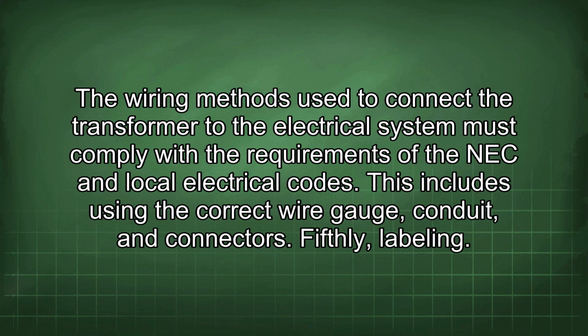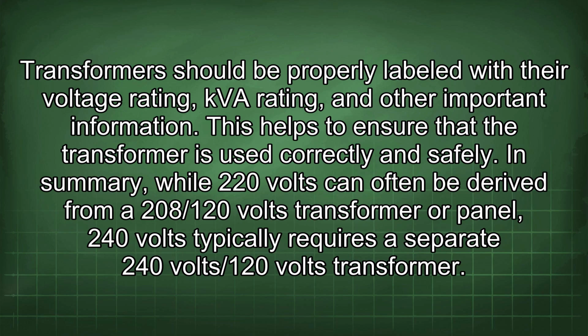Fifthly, labeling. Transformers should be properly labeled with their voltage rating, kVA rating, and other important information. This helps to ensure that the transformer is used correctly and safely. In summary, while 220 volts can often be derived from a 208/120 volts transformer or panel, 240 volts typically requires a separate 240 volts/120 volts transformer.